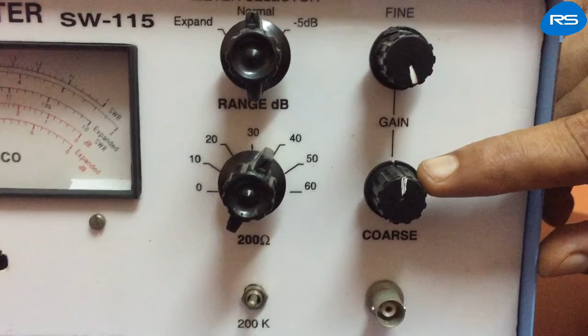We have a gain coarse control and fine control. Gain coarse control is a control for adjustment of meter on full scale or any other convenient reading. Gain fine control is used for fine adjustment of meter on full scale or any other convenient reading, maybe 0.8 dB.